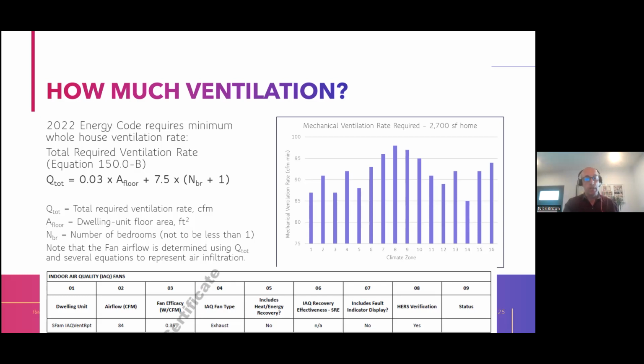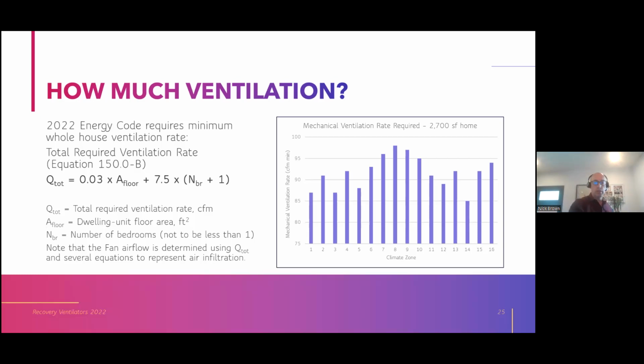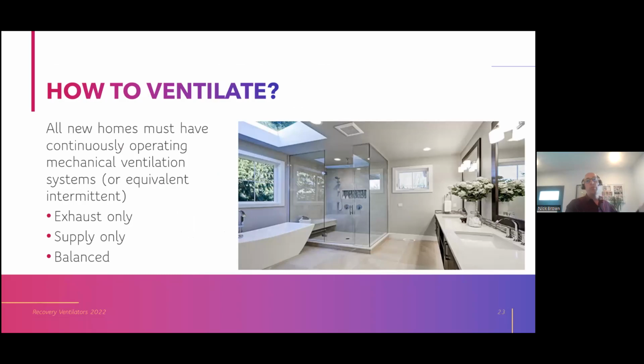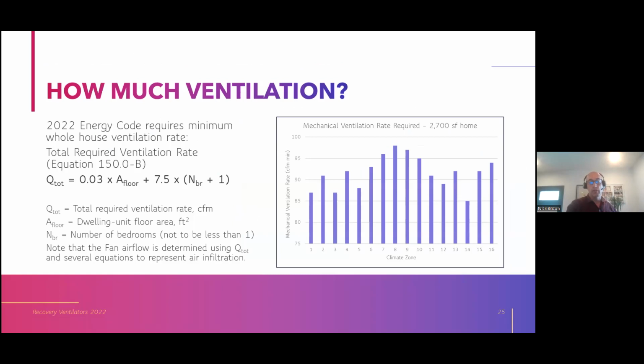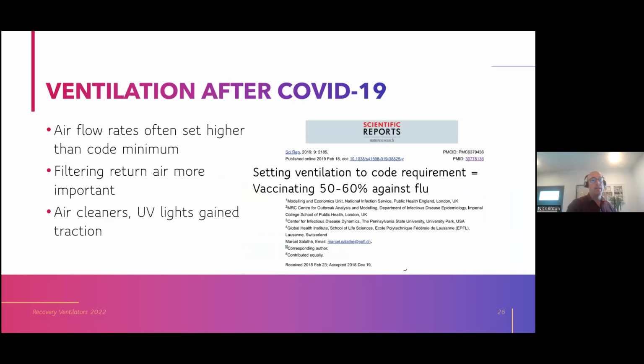And the HVAC system, all this outside air is being brought into our space, right? Well, our HVAC system has to condition that air. So in the exhaust scenario that we showed earlier, this bathroom setup, let's say we're bringing in 90 CFM of outside air. That's 90 CFM that our HVAC system has to heat and cool. When it's 100 degrees outside, that's a significant amount of air to cool. When it's 40 degrees outside, that's a significant amount of air to heat. That's where the energy savings comes from with recovery ventilators. And all that is happening in your energy code software beneath the hood.